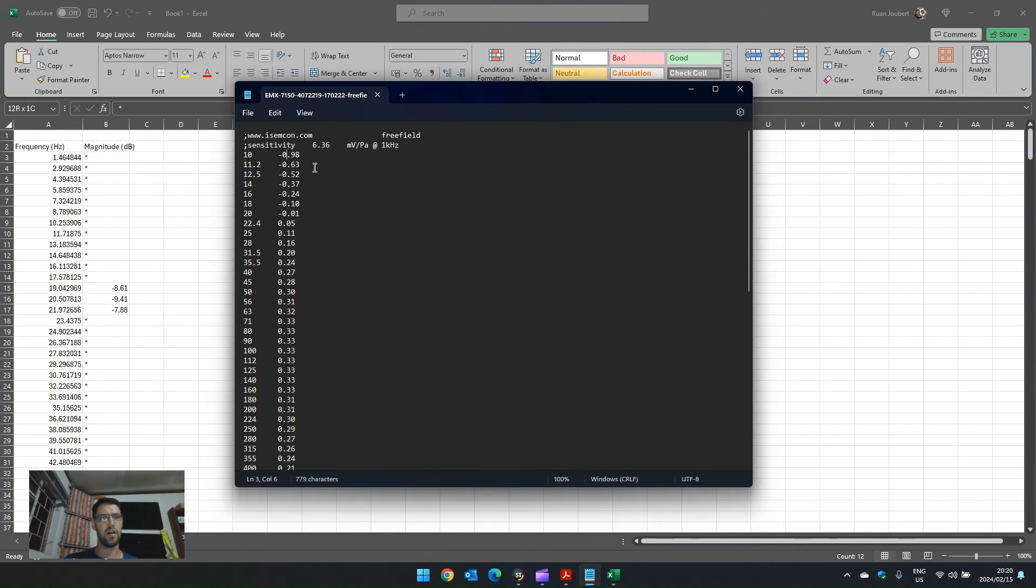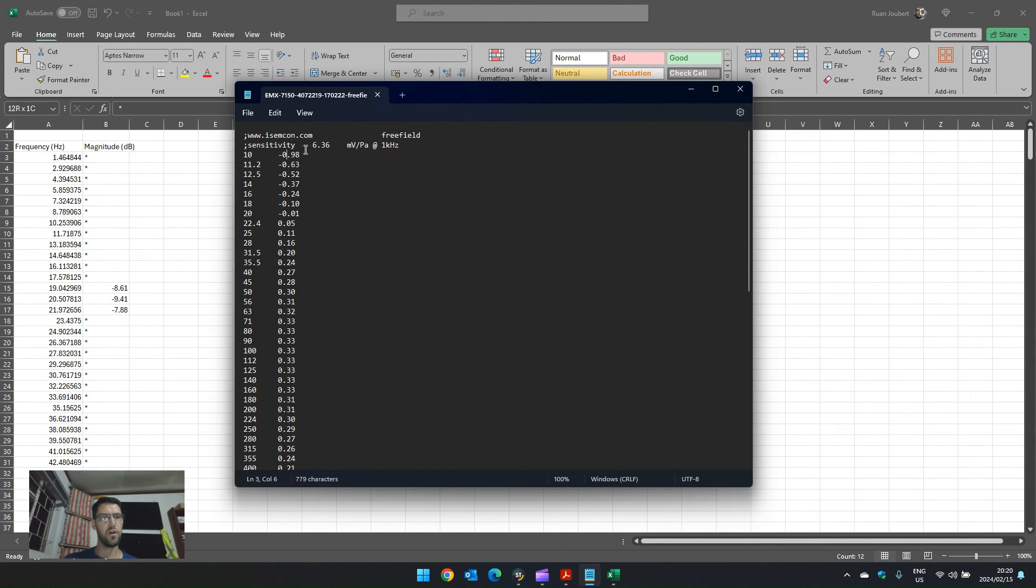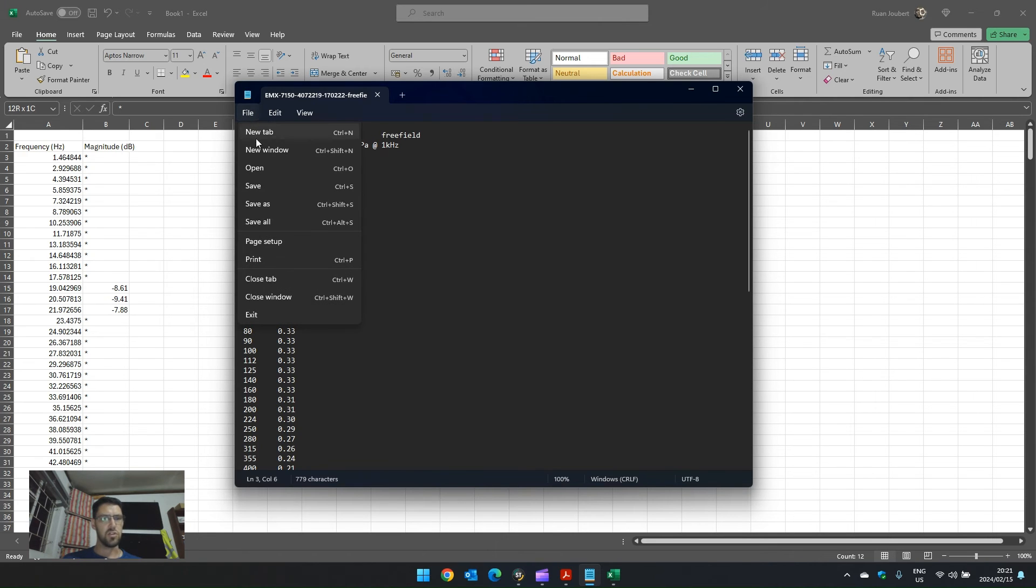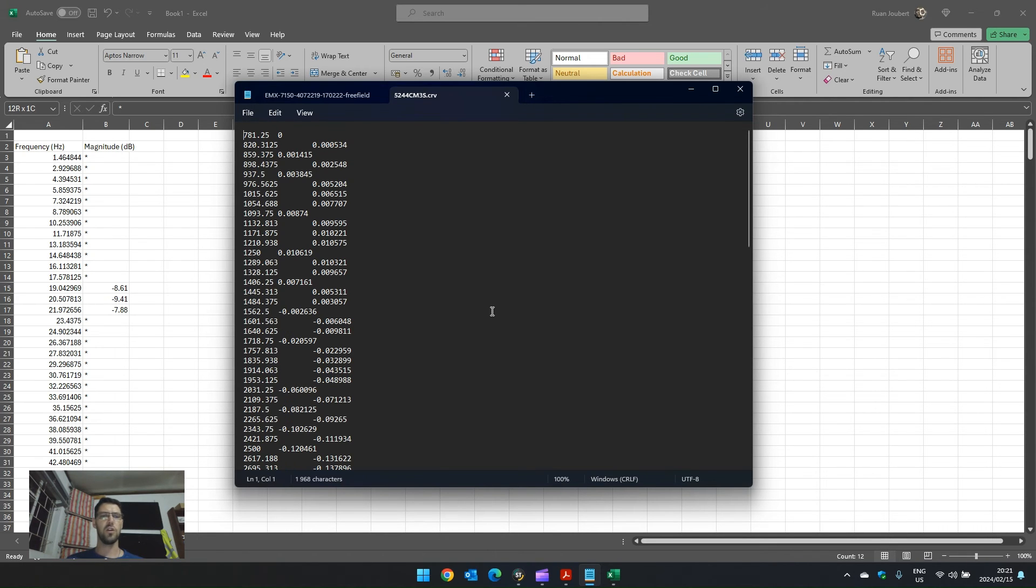So, if I go back to my text file, we can see that this ISEMcon file just has a bit of information about the microphone, gives me the sensitivity, but it doesn't actually give me headings in terms of frequency and magnitude. If I have a look at another correction file.